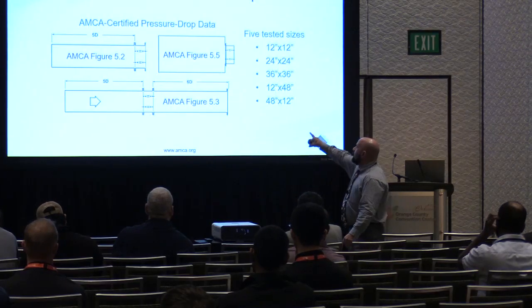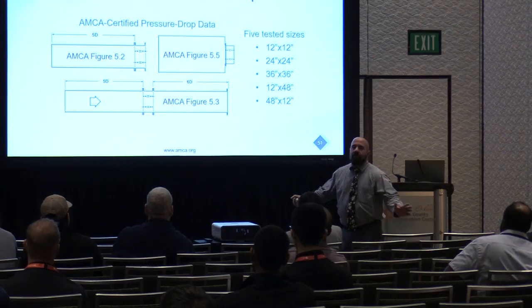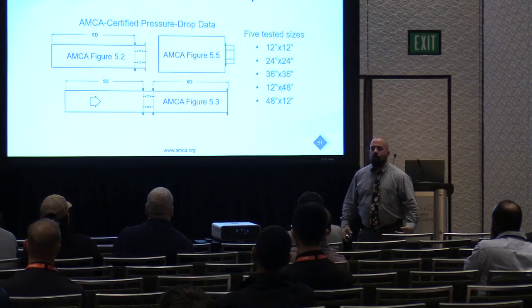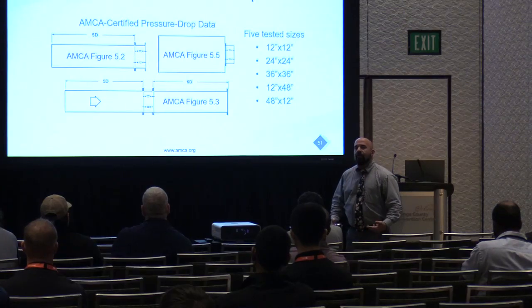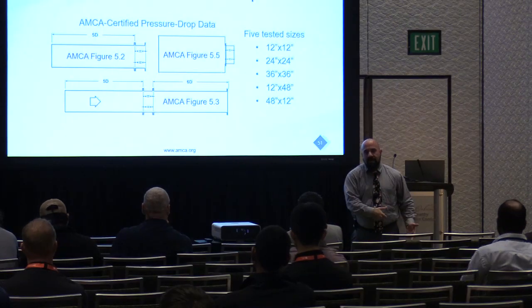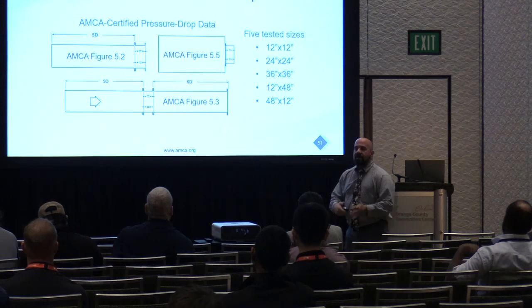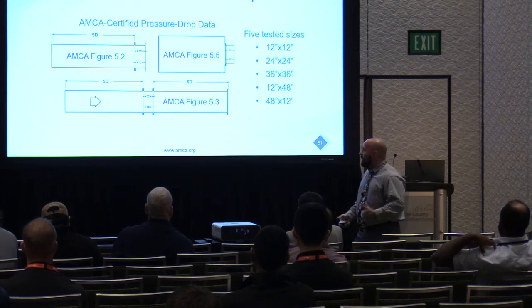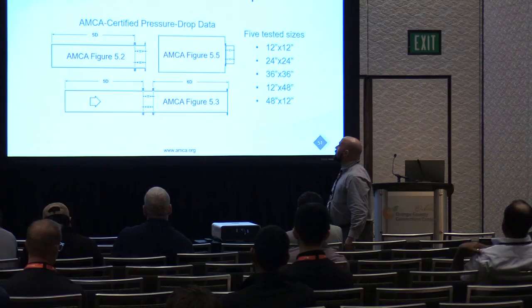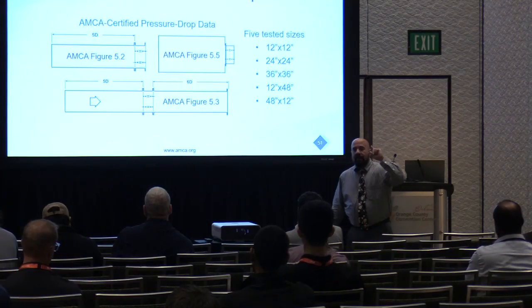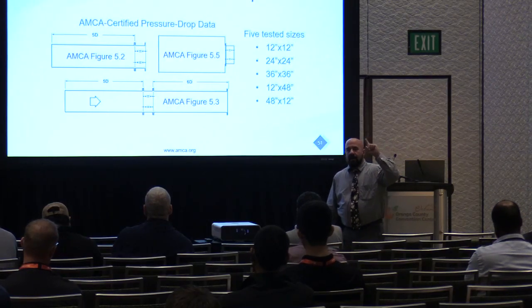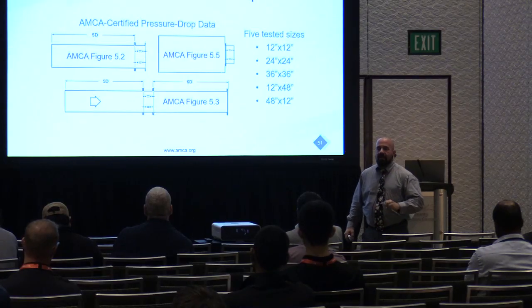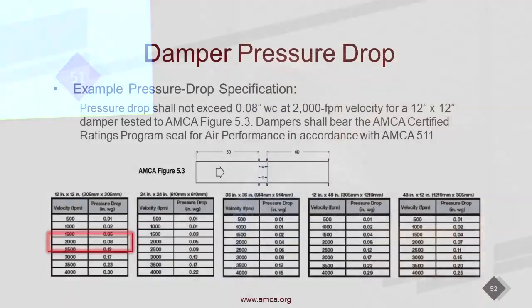So understand there are different figures. Not every manufacturer has this data available, but if you want to really design a high-performance system to ensure your fans, motors, and everything are sized appropriately and within fan input power levels and FEI and all that good stuff, think about the installation. It matters. Am I a grill-mounted damper? Am I a plenum-mounted damper? Do I have an elbow? Do I have a turning vane? Do I have all this other stuff in the ductwork that I don't know about that's going to create additional pressure drop? So be cognizant of that.